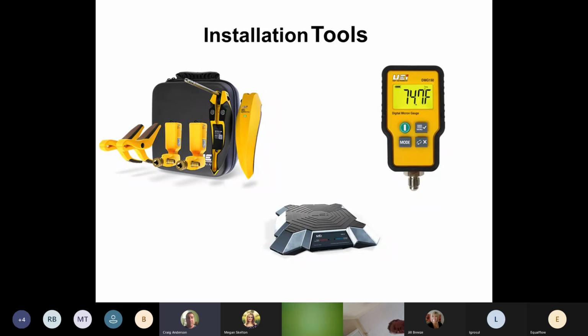Once you change the airflow, you're going to be able to check to see what that outdoor unit is doing. So if you're thinking about getting the new digital gauges that are going to tell you superheat, subcool, and all that, it's a great little piece of equipment to take a peek at if you're in the ballpark for it. It tells you everything: your subcooling, your superheat, temperatures. Great little machine.